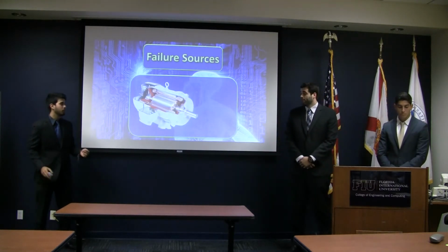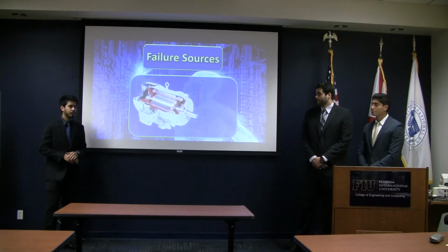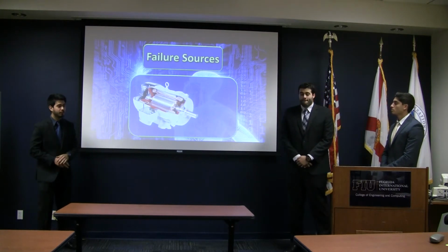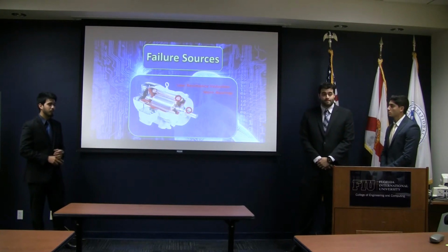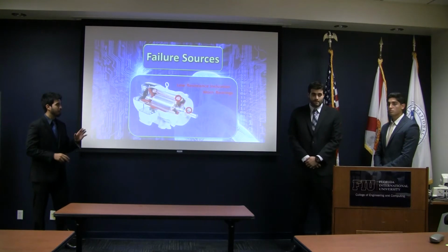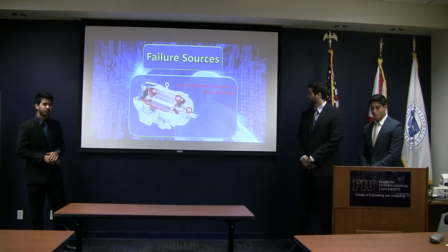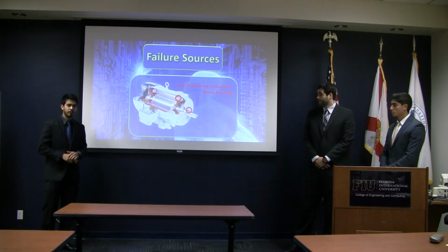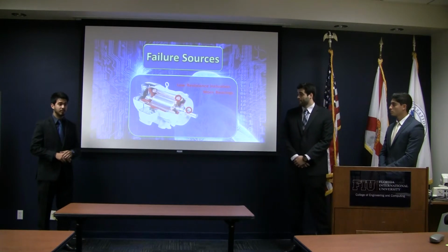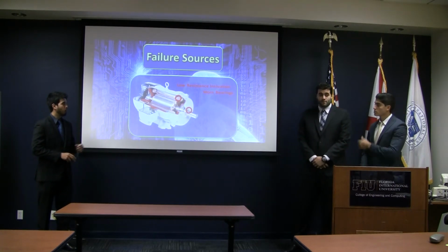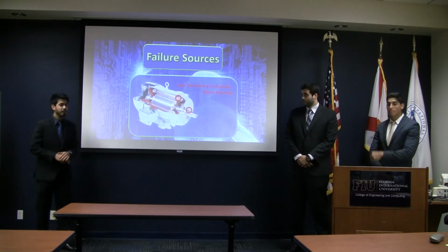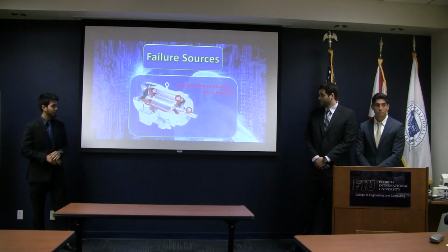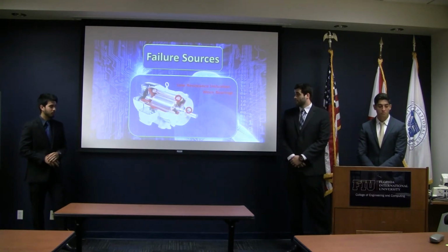A quick intro to the sources and symptoms of failure in large electric motors: looking at thermal aspects, the first giveaway is low resistance in the insulation. The copper windings start losing resistance and will eventually burn out. A worn or broken bearing causes an increase in temperature in the shaft, which can be measured and will ultimately lead to failure as well.